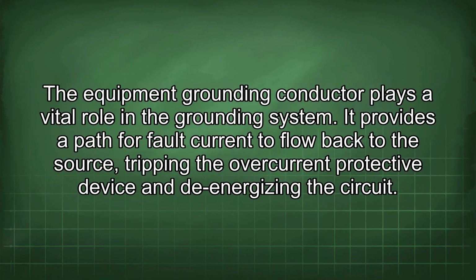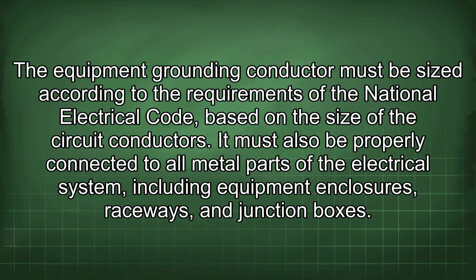The equipment grounding conductor plays a vital role in the grounding system. It provides a path for fault current to flow back to the source, tripping the overcurrent protective device and de-energizing the circuit. The equipment grounding conductor must be sized according to the requirements of the National Electrical Code, based on the size of the circuit conductors.